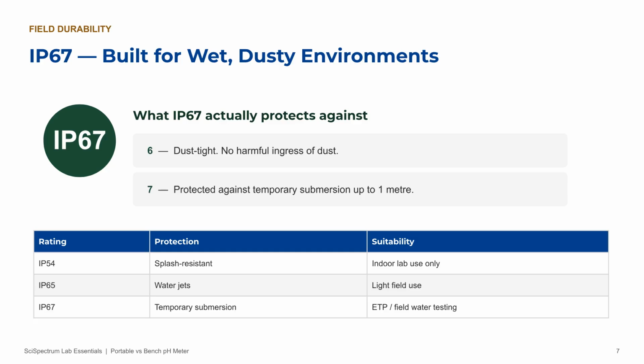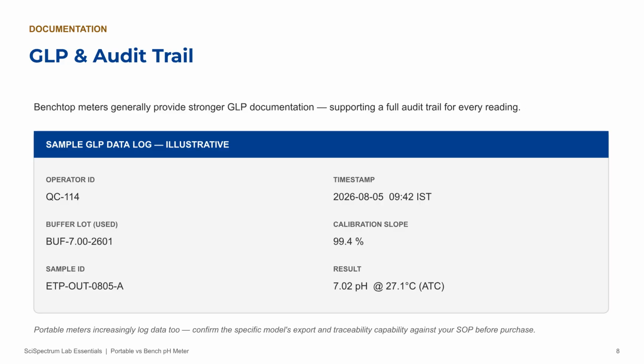Benchtop instruments simply aren't built for that, and you shouldn't take them into it. Now, for anyone working under GLP, pharma QC especially, documentation is often the deciding factor. Benchtop meters generally give you stronger data logging, GLP printouts, USB or RS-232 export, sometimes even a direct LIMS connection. That's what supports a full audit trail. Who calibrated, when, with which buffer lot, what the slope was. You can see a sample log here.